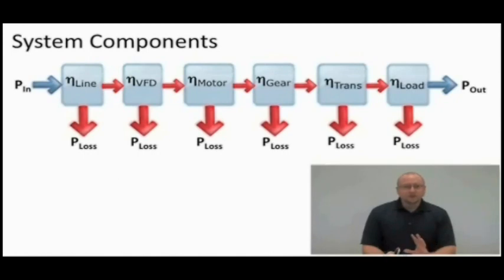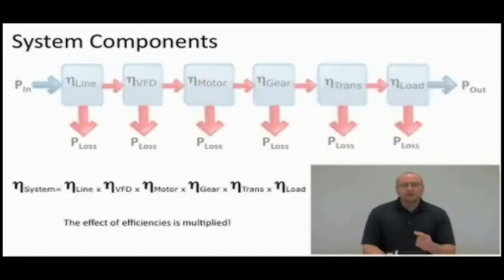But what's really interesting is, do you know how these efficiencies relate to each other? The effect is actually multiplied. So each little inefficiency is multiplied throughout the system. So you could have a really good high efficiency motor directly coupled to your load, but if you have a poor efficiency gearbox in between there, you lose all the benefit of buying that premium efficiency motor. So that's something we need to take a look at and try to fit into the big picture of our system, look at all the individual components and see if they make sense adding together? Well, not adding together, but multiplying together.